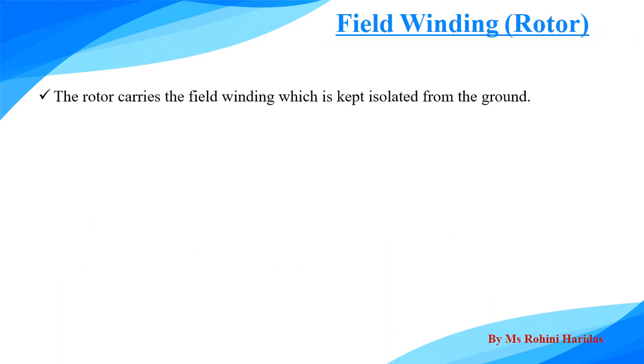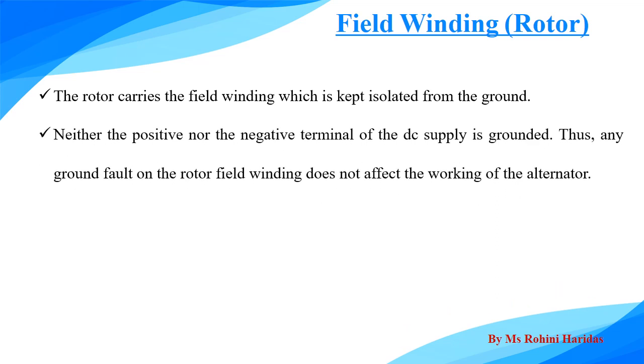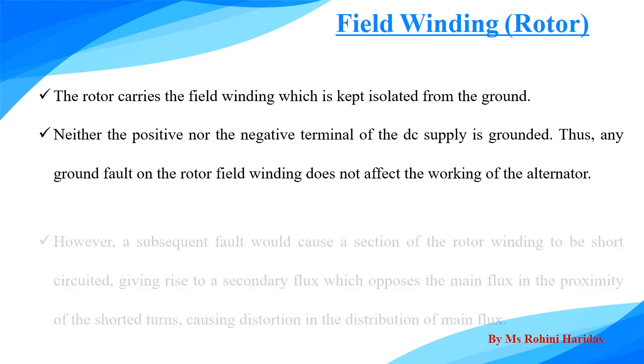Field winding, that is the faults on the rotor side. We know that the rotor carries the field winding which is kept isolated from the ground. That is, neither positive nor negative terminal of the DC supply is grounded and therefore, any ground fault on the rotor field does not affect the working of the alternator.